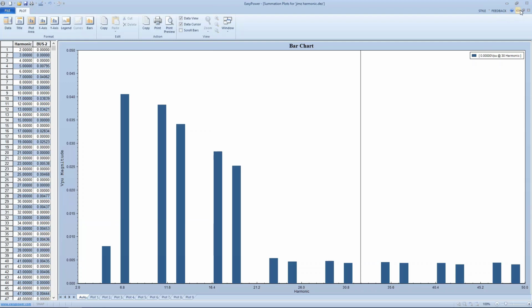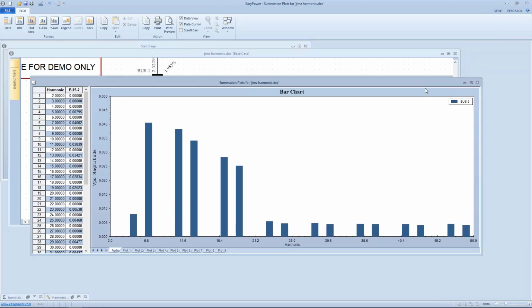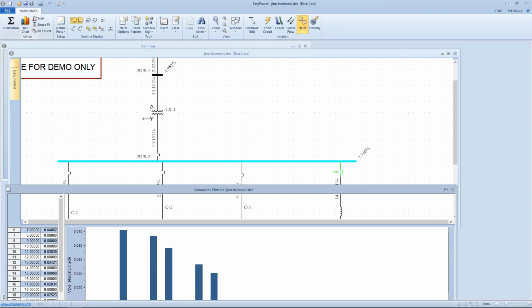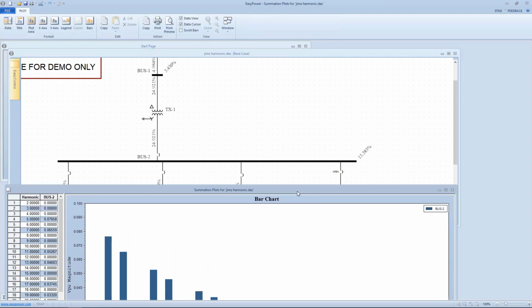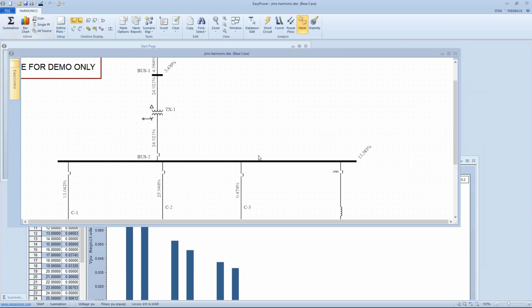So what I wanted to do is to show you the change if I take my filter in and out. So let's take the filter out, and I can see that now my fifth harmonic is back in the system. So the capabilities of the tools give me the ability to go through a fairly significant span of what ifs in terms of the sources.